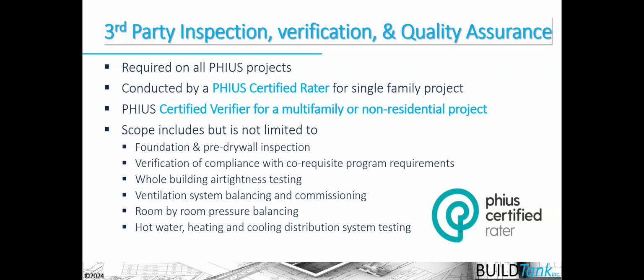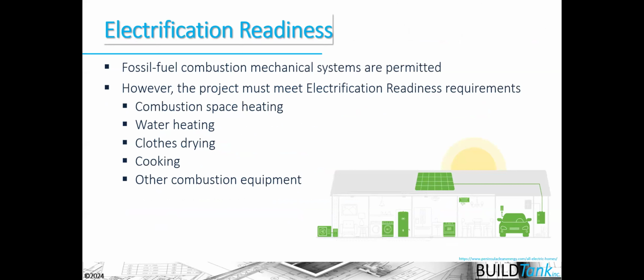You can see some of the things the certifier or rater would be looking at and the inspections they'd go through. This is most specific to the single-family realm: whole building air tightness testing, and room by room pressure balancing for sure — that's a requirement of the DOE Zero Energy Ready Home program incorporated here. You need to look at all these things, test and verify them, and do it not only at the end of construction but also foundation and pre-drywall inspections.